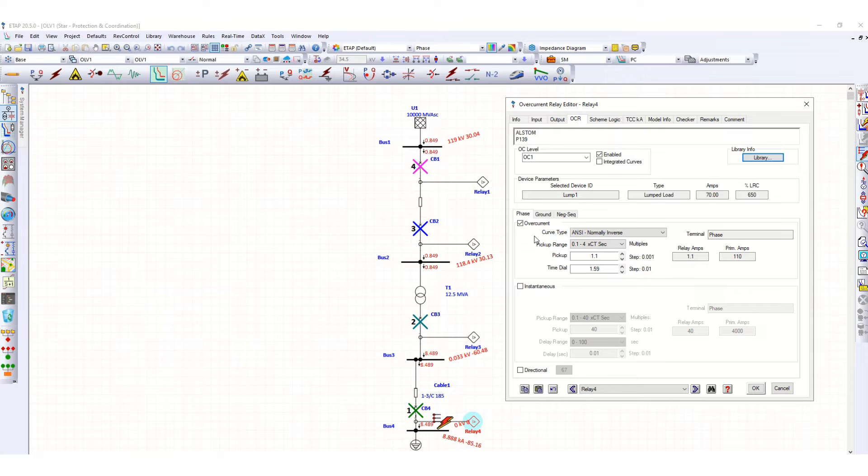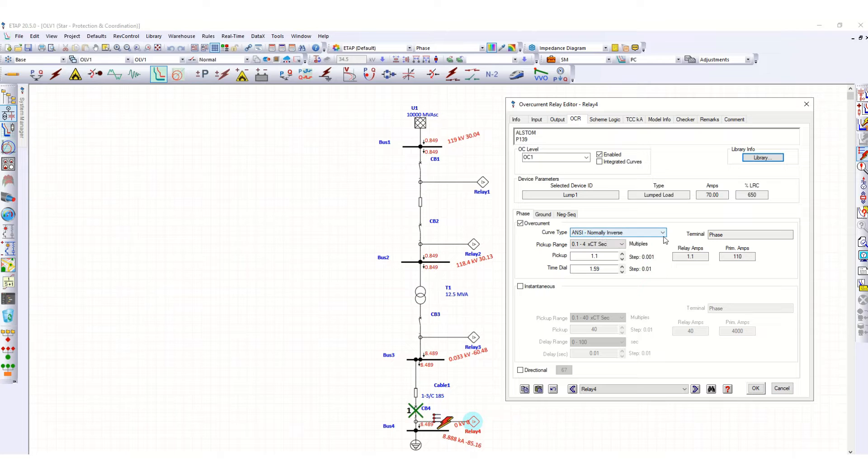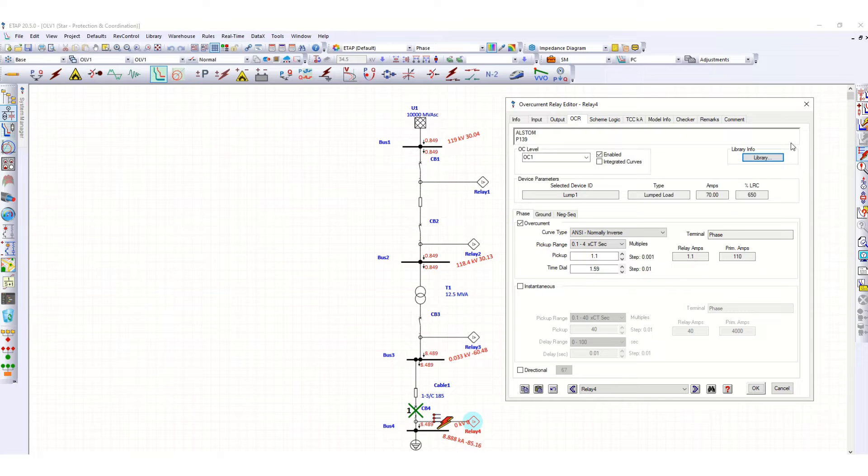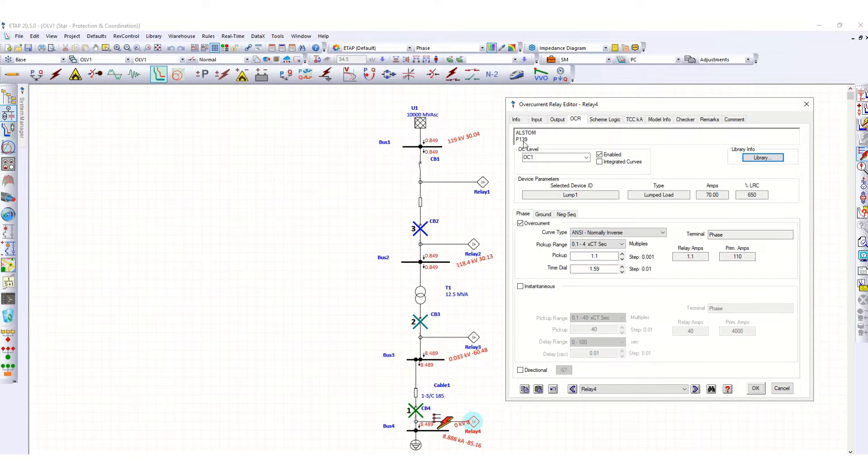We have selected the normally inverse characteristic, and the pickup is 1.1 and time dial is 1.59. We have selected this Alstom P139 overcurrent relay.